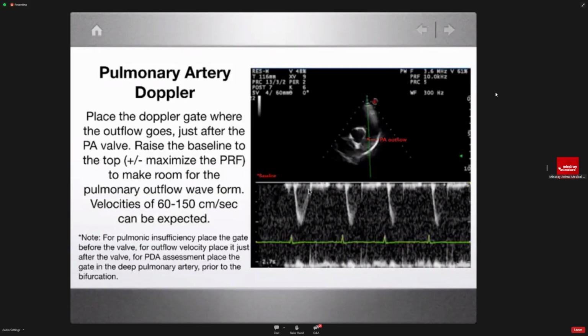Give yourself space for that waveform to fill in within the space provided. Okay, and you can maximize your PRF, and that'll give you more space to work with. So the PRF is set at 2.7 maximum meters per second. So this is about 1 meter per second on the outflow velocity, which is normal.